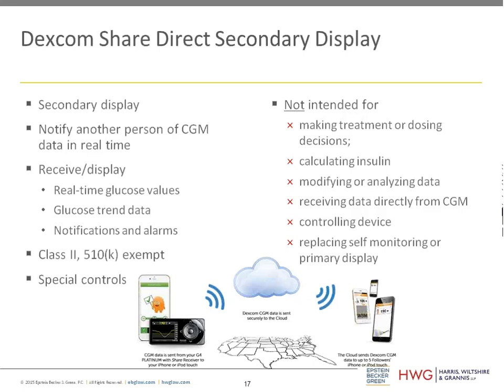And this is a great example of application of the draft guidance. Now, I do highlight some of the things it's not intended to do, and those are going to be considered higher risk activities. So it's not making treatment decisions, dosing decisions, not calculating the insulin or modifying the data in any way, controlling the device. Importantly, it's not replacing the individual's obligation to self-monitor, but also it's not serving as the primary display. It is just a secondary display and secondary notification.